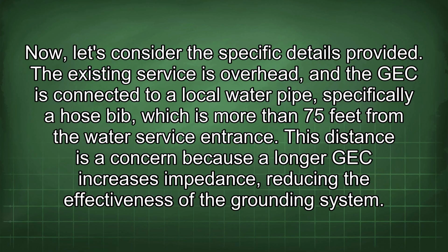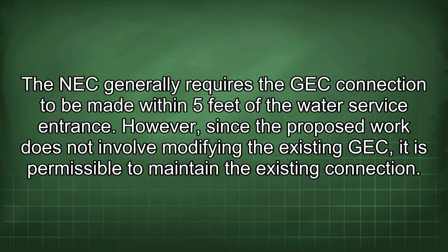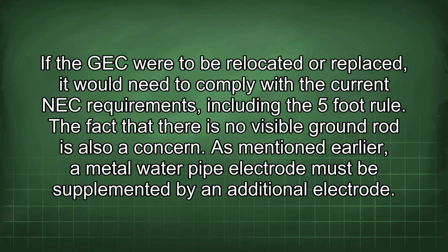The existing service is overhead, and the GEC is connected to a local water pipe, specifically a hose bib, which is more than 75 feet from the water service entrance. This distance is a concern because the longer GEC increases impedance, reducing the effectiveness of the grounding system. The NEC generally requires the GEC connection to be made within 5 feet of the water service entrance. However, since the proposed work does not involve modifying the existing GEC, it is permissible to maintain the existing connection. If the GEC were to be relocated or replaced, it would need to comply with the current NEC requirements, including the 5-foot rule. The fact that there is no visible ground rod is also a concern.